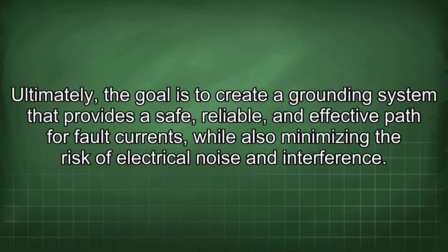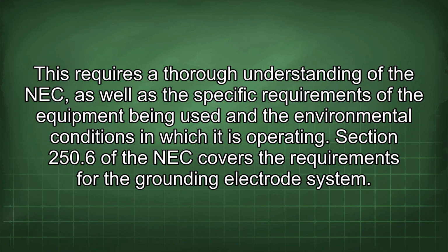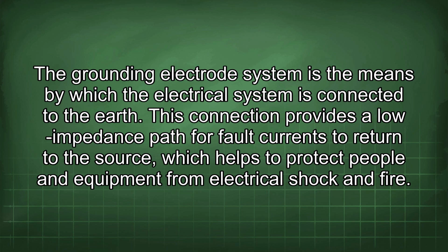applicable requirements. Ultimately, the goal is to create a grounding system that provides a safe, reliable, and effective path for fault currents, while also minimizing the risk of electrical noise and interference. This requires a thorough understanding of the NEC, as well as the specific requirements of the equipment being used and the environmental conditions in which it is operating. Section 250.6 of the NEC covers the requirements for the grounding electrode system. The grounding electrode system is the means by which the electrical system is connected to the earth. This connection provides a low impedance path for fault currents to return to the source, which helps to protect people and equipment from electrical shock and fire.